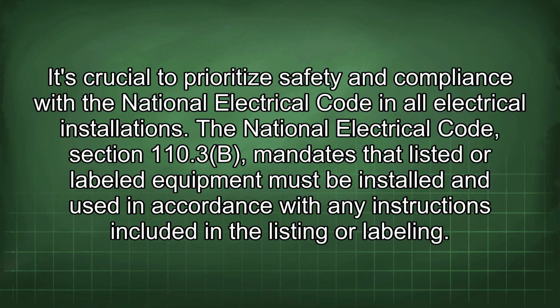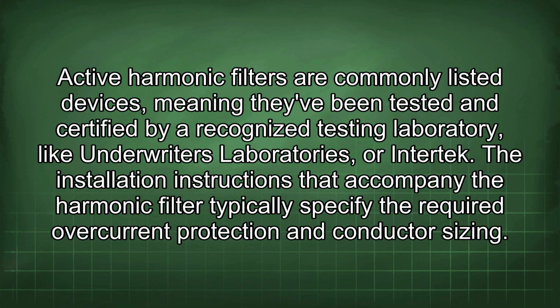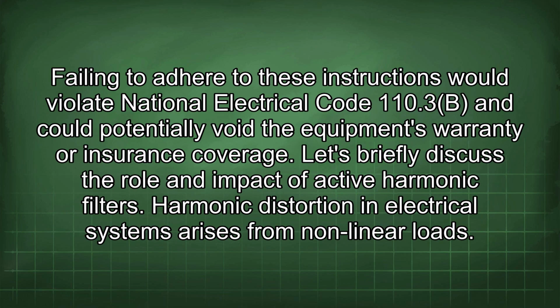The National Electrical Code, section 110.3(B), mandates that listed or labeled equipment must be installed and used in accordance with any instructions included in the listing or labeling. Active harmonic filters are commonly listed devices, meaning they've been tested and certified by a recognized testing laboratory like Underwriters Laboratories or Intertek. The installation instructions that accompany the harmonic filter typically specify the required overcurrent protection and conductor sizing. Failing to adhere to these instructions would violate National Electrical Code 110.3(B) and could potentially void the equipment's warranty or insurance coverage. Let's briefly discuss the role and impact of active harmonic filters.